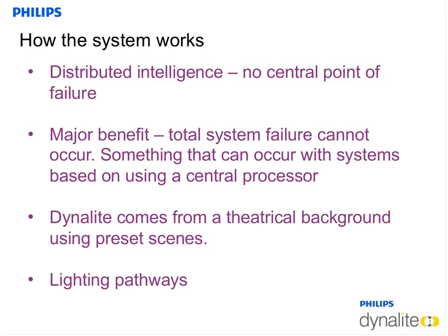So I say scene number one: my ceiling lights are off, my reading light's on, my wall lights are on. Scene two might be another mixture of this. And all of these are loaded as scenes or presets in our system, and we can point different presets to each button to tell that button to carry out that preset. And by combining different presets in different rooms, we can create what we call pathways.